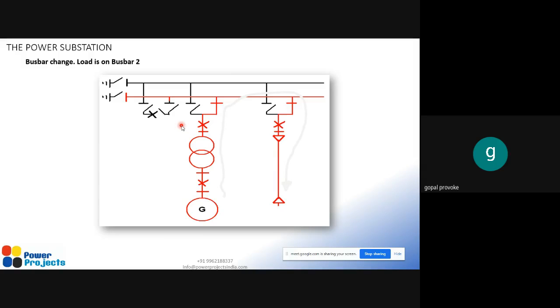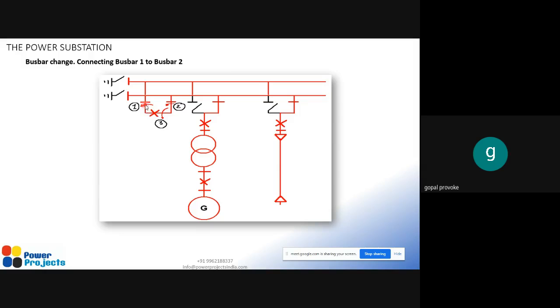So first, as you saw before, we want to close the isolators. We will close the isolator first, and again we will close the second isolator, and third we will close the breaker. So the X mark is the breaker. We will close the breaker third. After closing this, the supply from the bottom bus bar will be transmitted to the other bus bar.